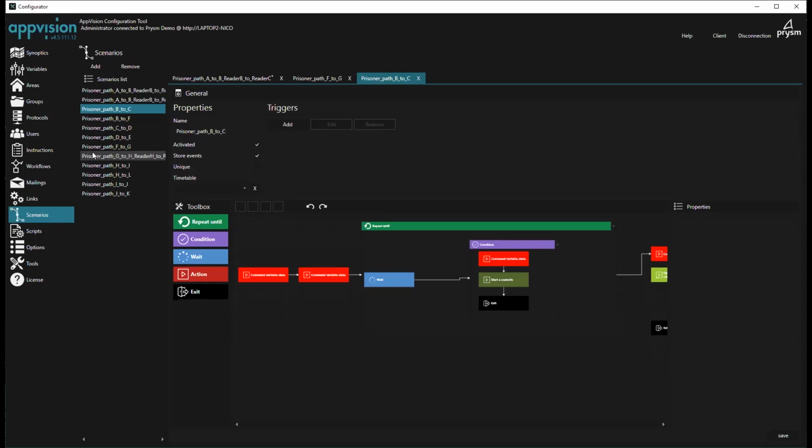So it means you will filter the alarm list of one user profile to some alarm severity list. But if you want to dedicate one alarm to someone, so to transfer one alarm to someone, for the moment you have to do it by script. So you can use the severity level as a trigger to do the transfer to another user.